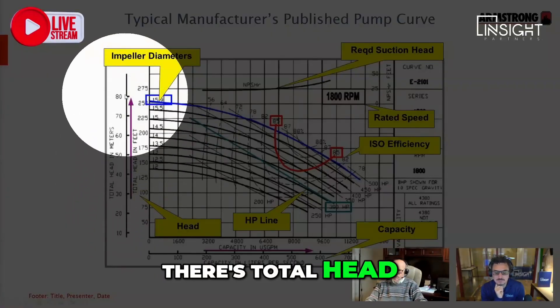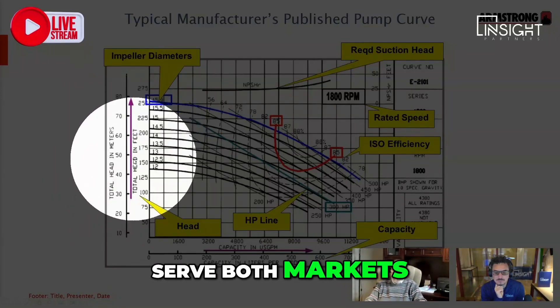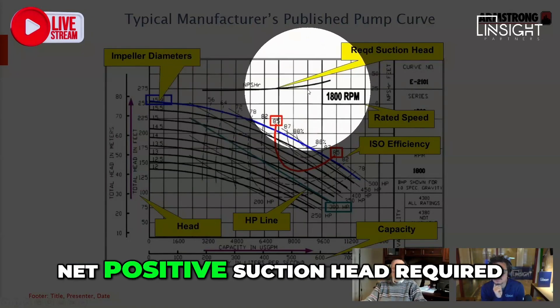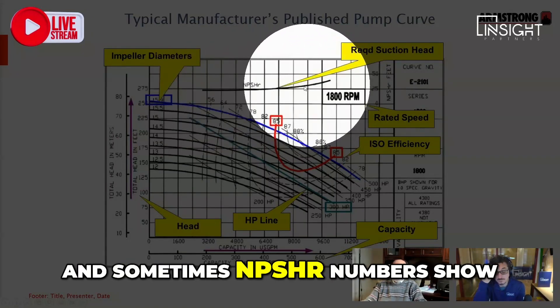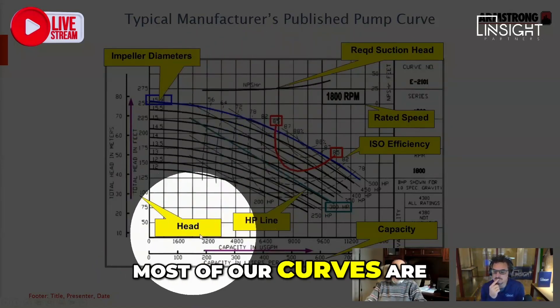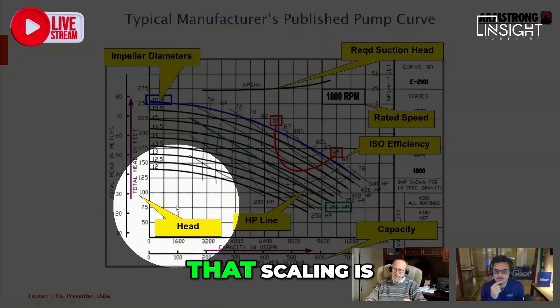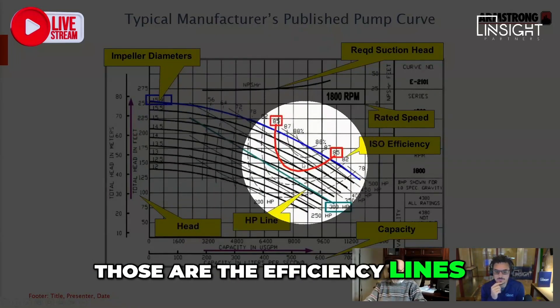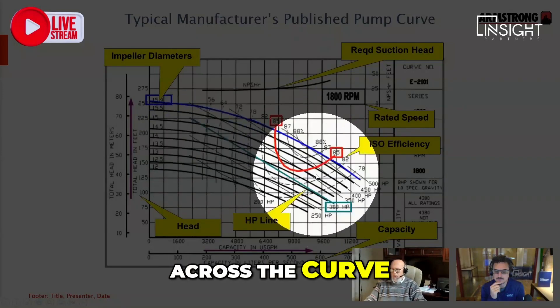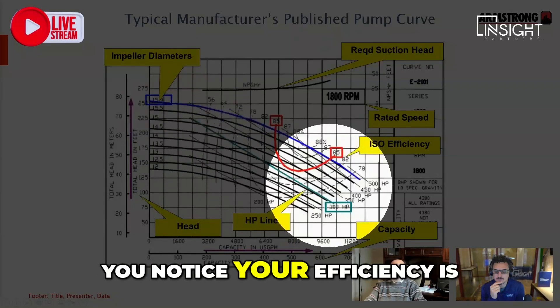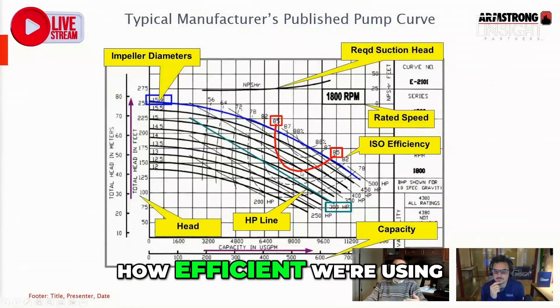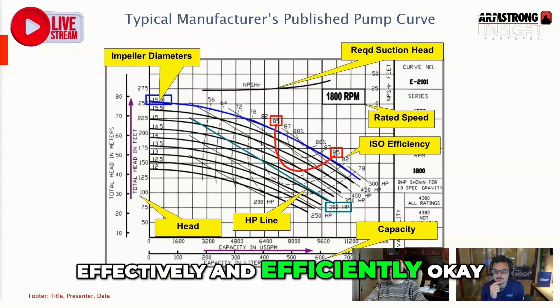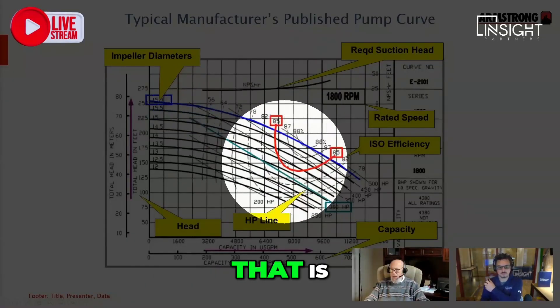Nothing's changed. There's total head in both feet and meters because we've got to serve both markets. There's our headline, there's our impeller diameters. We have another line on here called NPSHR, which is net positive suction head required. Sometimes NPSHR numbers show up at the top, sometimes they're down at the bottom. Most of our curves they're down at the bottom, and there's a chart that'll tell you what that scaling is. Then the next thing you see is these isoefficiency lines on the curve — those are the efficiency lines. As you move back and forth across the curve with different impeller sizes, you notice your efficiency is moving around — that's how efficiently we're using the motor power. And then this last line here, this green line, that is our motor horsepower line.